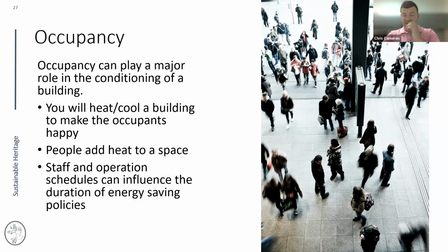When they backed that down to 68 degrees, they had such a high occupancy from visitors in their museum that just the presence of a high number of people raised the temperature in the space back up to, I think it was about 70 degrees. So just the body heat from visitors in this very large museum was artificially raising that temperature up to 70 degrees.